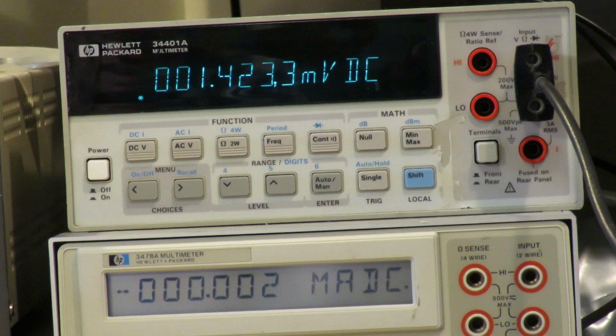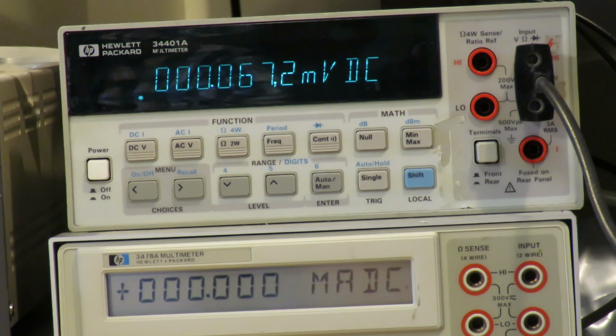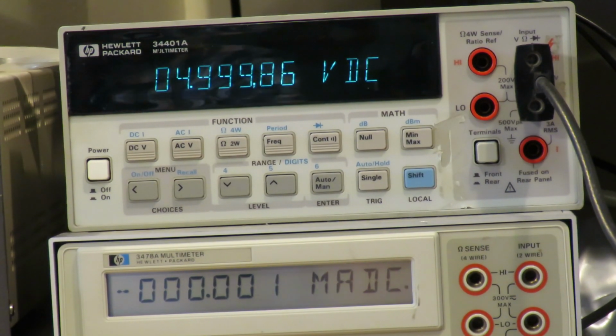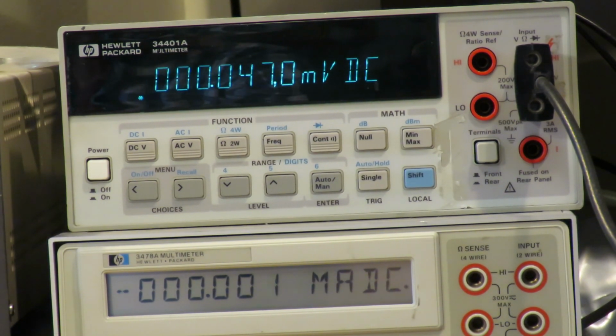And then on the 15 volt range, you get 10 times the resolution and a little bit lower noise. And you can see there's 5 volts, 4.99. Lots of 9s, not quite enough. The calibration is not perfect. I haven't calibrated this thing in quite a while. Minus 5. And offset error of about 0.06 millivolts, so 60 microvolts. So that's pretty good.